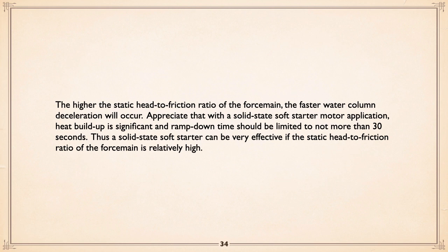But as I say, the solid state starter can apply energy on ramp down, which will control how the discharge head comes down. But you're limited to about 30 seconds. So if you've got something that is going to come down quicker than that, the solid state starter with ramp down will make a heck of a difference.